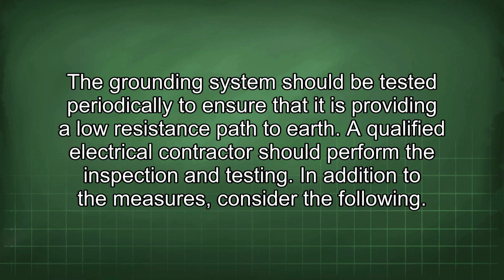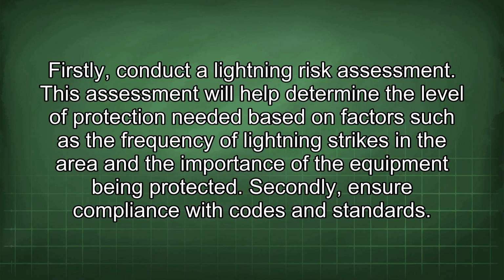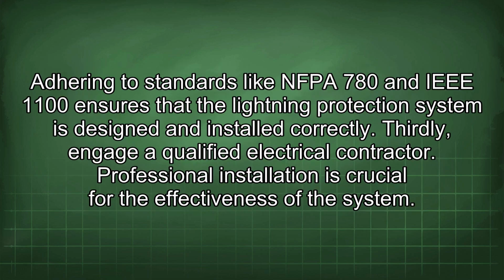In addition to these measures, consider the following. Firstly, conduct a lightning risk assessment. This assessment will help determine the level of protection needed based on factors such as the frequency of lightning strikes in the area and the importance of the equipment being protected. Secondly, ensure compliance with codes and standards. Adhering to standards like NFPA 780 and IEEE 1100 ensures that the lightning protection system is designed and installed correctly.